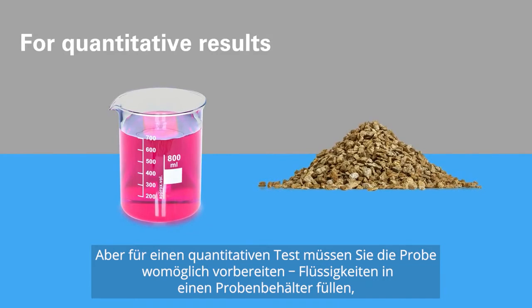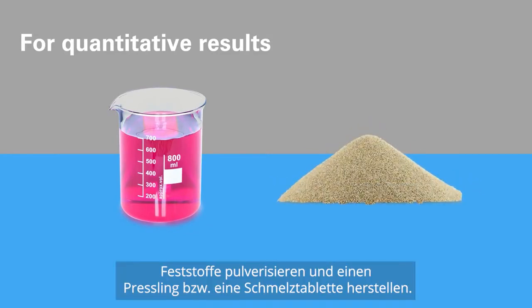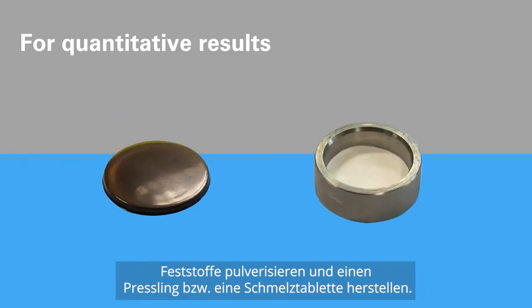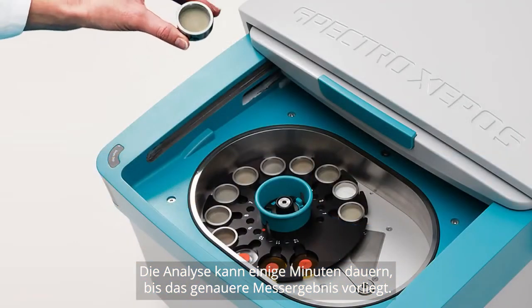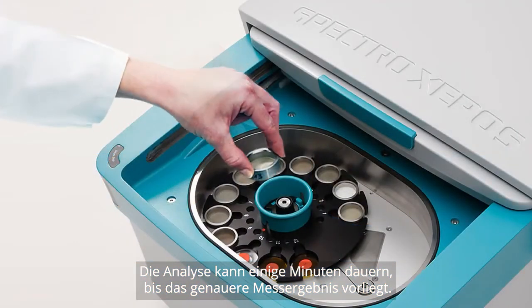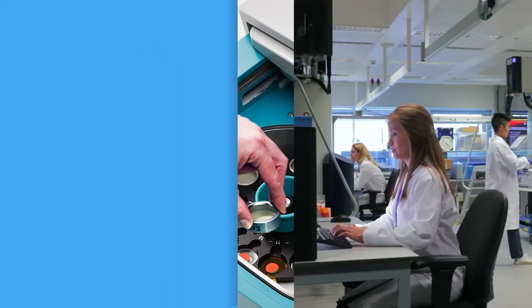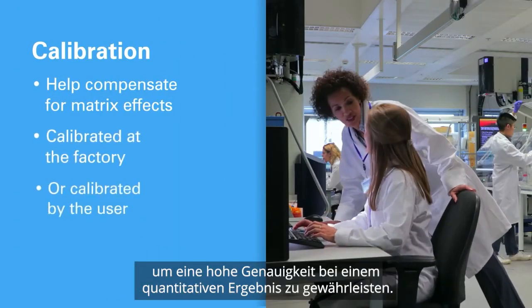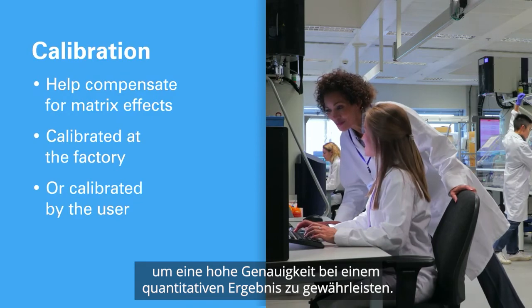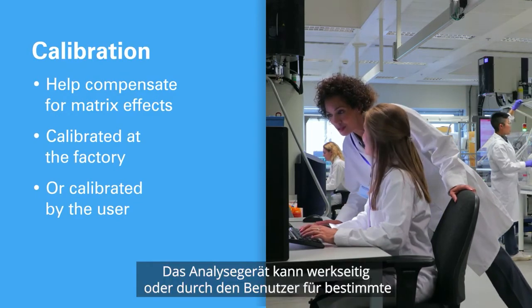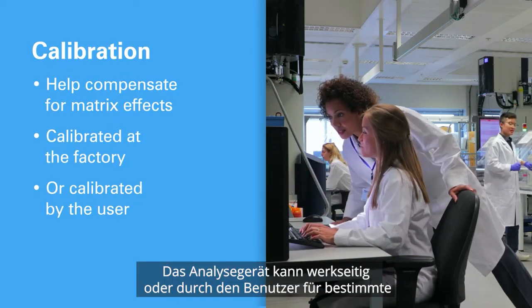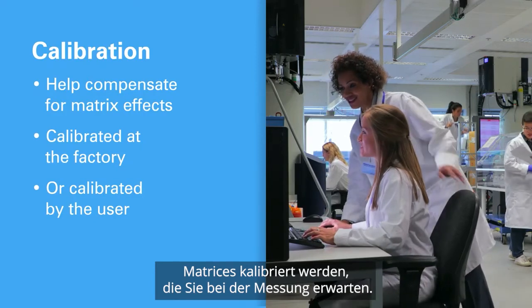But for a quantitative test, you may have to prepare the sample: fill liquids into a sample cup, pulverize solids and make a pressed pellet, or fused bead. Analysis may take a few minutes for this more accurate result. Correct calibration is also critical to ensure high accuracy in a quantitative result.